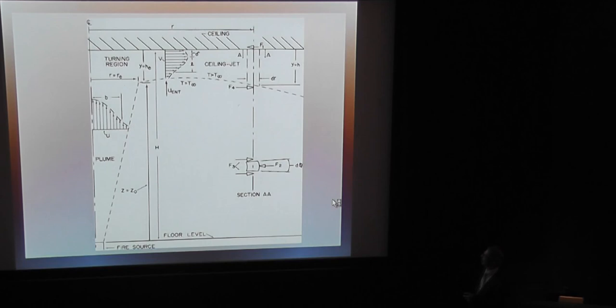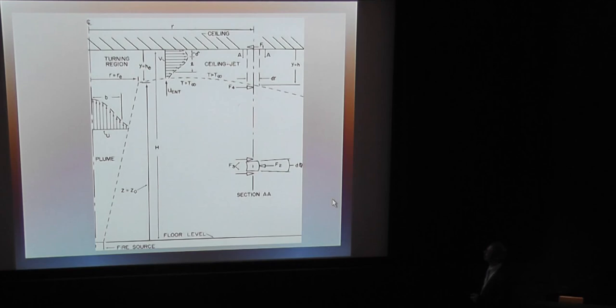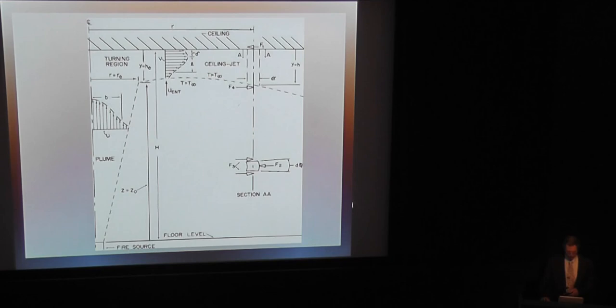Later work done here at Interflam showed that a lot of energy is actually lost in that turning, but that's the assumption made in the original model. There's a small distance below the ceiling where you have drag from the ceiling boundary layer, so the maximum velocity is somewhat below the ceiling. In many of the measurements I'll be talking about, because they were on such a large scale, we weren't able to carefully determine exactly where the maximum velocity and temperature were, so take that with a grain of salt.